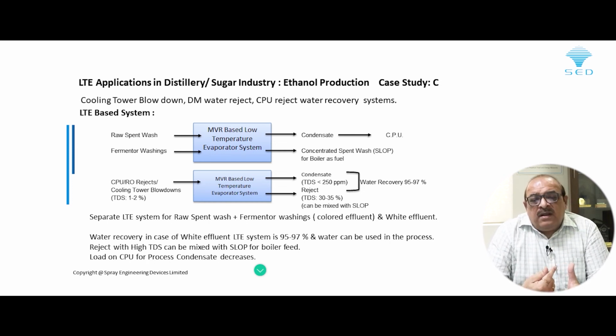Now instead of that, let the CPU RO rejects and cooling tower blowdowns combine together and feed them to another low temperature evaporator, where you are going to get very small operating power cost requirements. Generally speaking, the TDS is 1 to 2%, or in some cases 3% solids. Now to concentrate these solids, we can concentrate up to 35% or maybe 40% max. After that, you don't require more, because when you are concentrating to 30% or 35%, you have already recovered about 95 to 97% of your water. And concentrating inorganics and taking the water out is a very easy process, easy to handle.